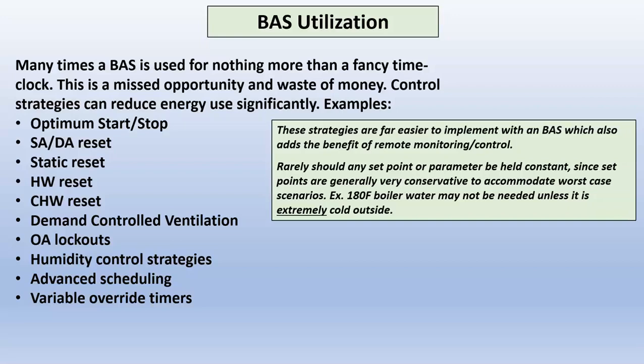Same strategy with a static reset. Basically, my variable frequency drive is meeting a set point that's in a duct static set point. That's what's determining the speed of the variable frequency drive. Well, if I don't need all that much, maybe when it's real mild outside, I should change that so my VFD doesn't have to work as hard. So I have 2 set points instead of 1.